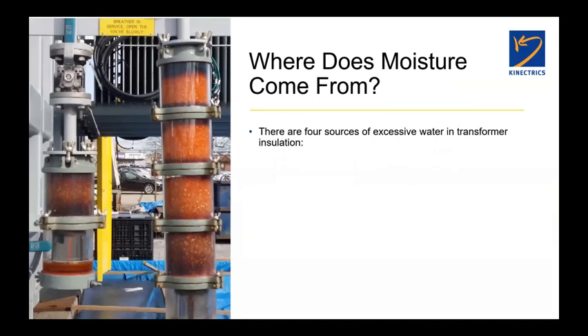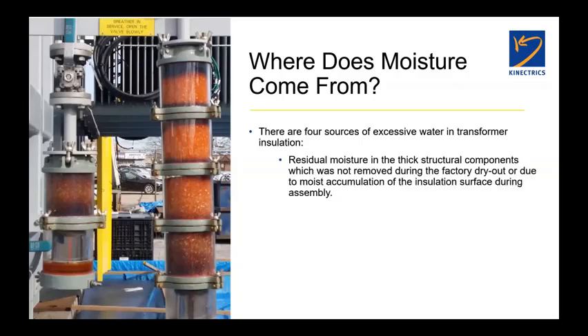So we know moisture's bad. We know the effects that it can cause. Where does moisture come from in a transformer? There are four basic sources of excess water in transformer insulation. The first is when you buy a new transformer from the factory, it comes along with a little present. And the little present is some water that's still left in the insulation.